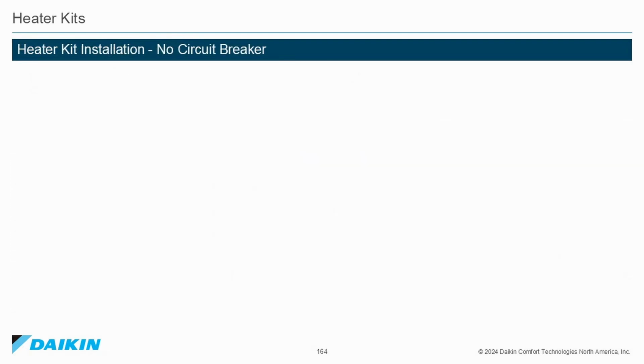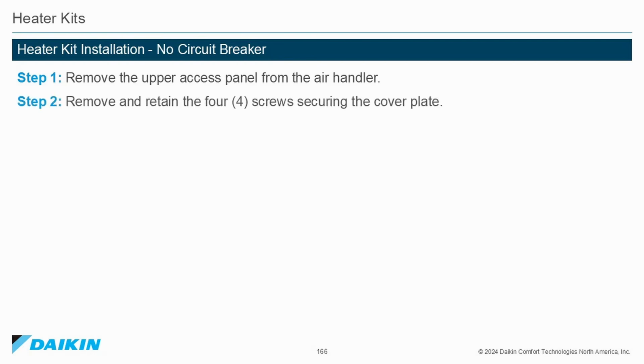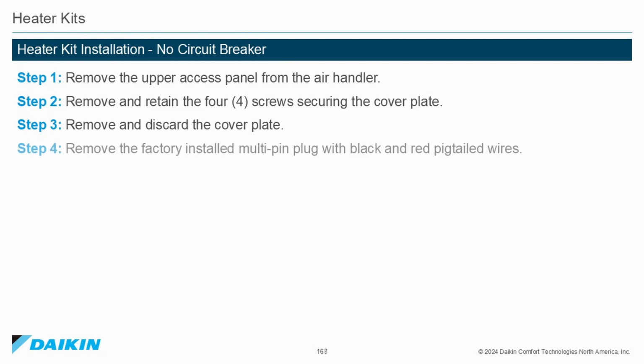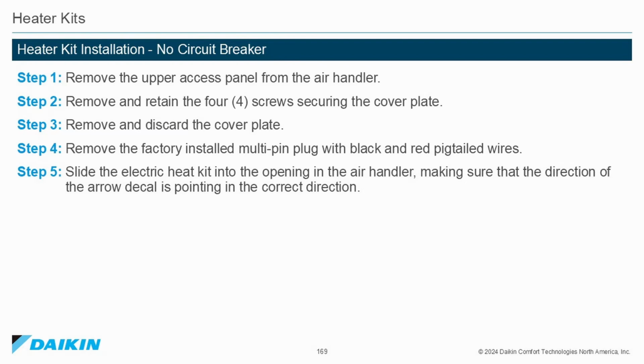For heater kit installation with no circuit breaker, Step 1. Remove the upper access panel from the air handler. Step 2. Remove and retain the 4 screws securing the cover plate. Step 3. Remove and discard the cover plate. Step 4. Remove the factory-installed multi-pin plug with the black and red pigtailed wires. Step 5. Slide the electric heat kit into the opening in the air handler, making sure that the direction of the arrow decal is pointing in the correct direction.